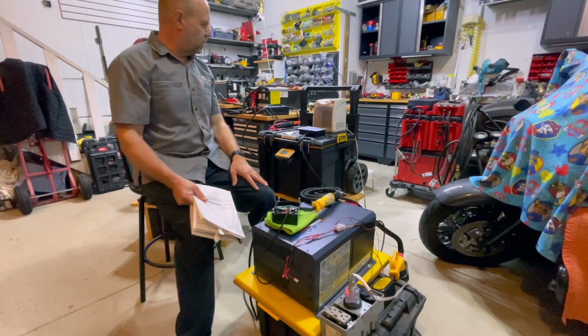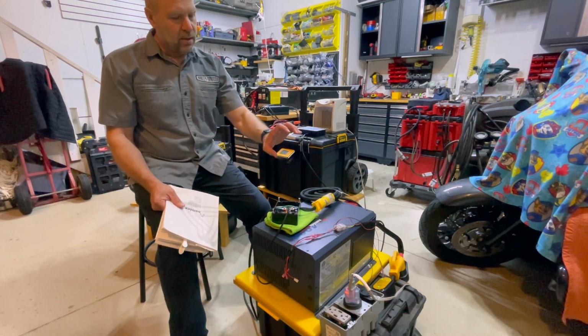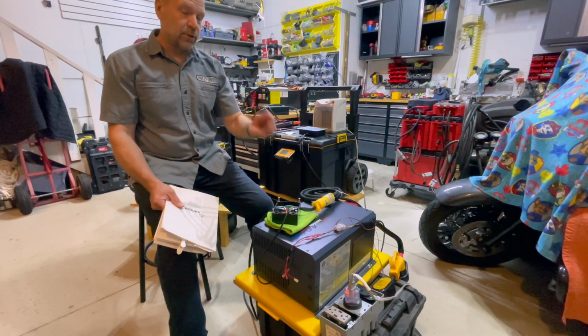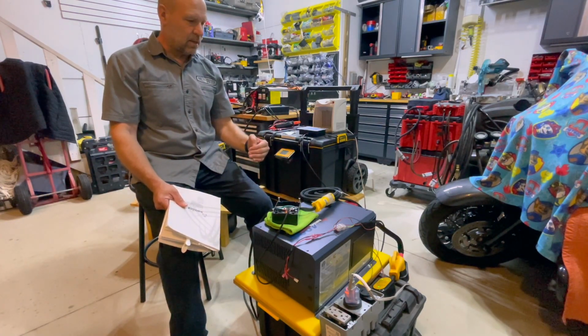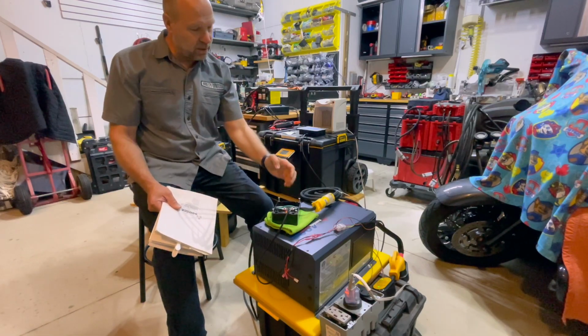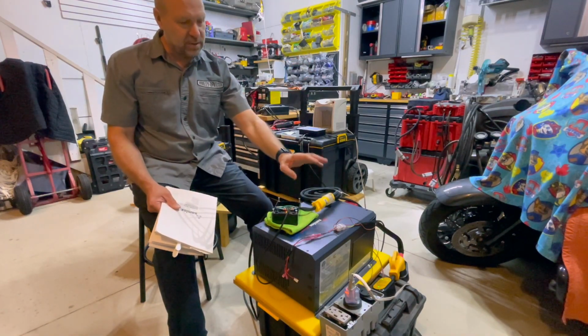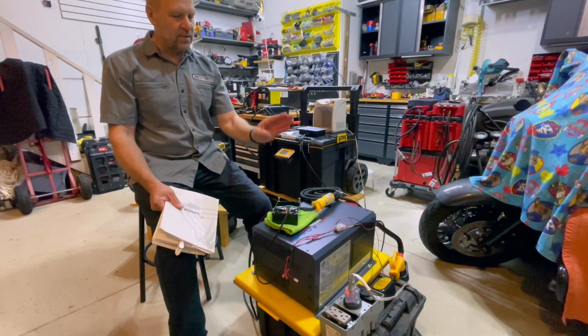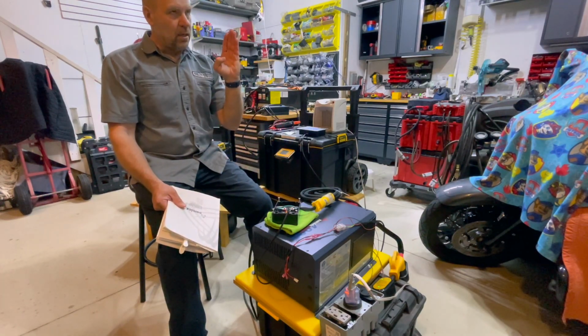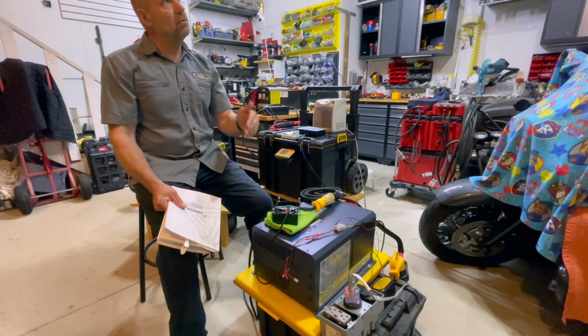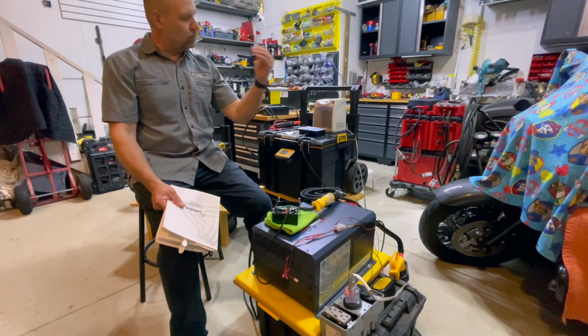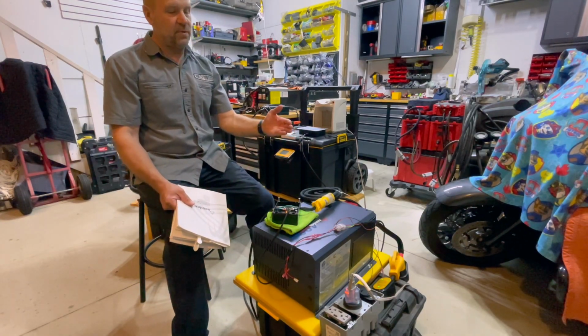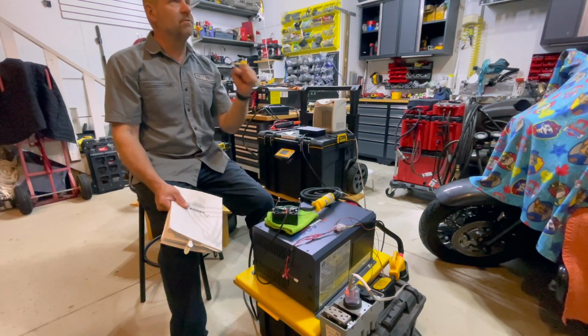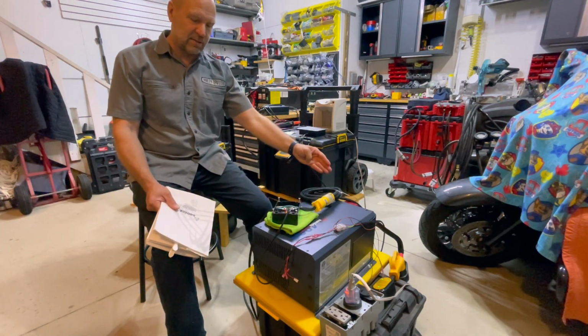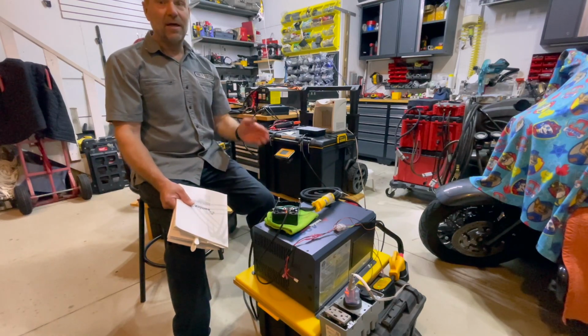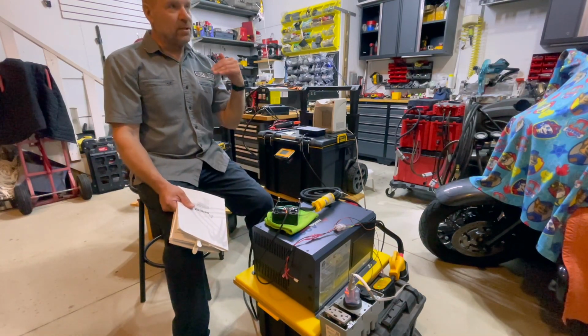The problem I've come across is that even though I tell the inverter to turn off because of a low battery state of charge, SOC, if this sees AC -- this is single phase -- if it sees AC 120, it'll stay on. Even though the batteries are really low and it still wants to invert, and I told it to shut off, that function has given the signal to the inverter, but it's still trying to invert right to the point where it shuts off.